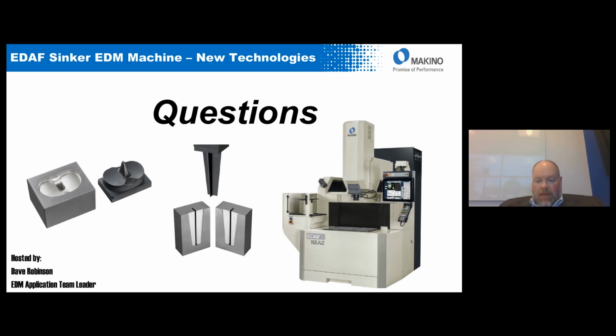Another question. We have a 2019 EDAF 3 heat. Do you recommend using a manifold to move the fluid more in the work tank? On the older machines, yeah, it's not a bad idea to use a manifold system to move that oil around. One of the problems, though, is when you do use a manifold system, you really have to watch running the oil across the top of the workpiece, across the top surface, either from front to back, which is generally the preferred method, or side to side if you have to. Setting up a manifold where that flow pushes the debris down into corners and pockets where it can get trapped can actually be counterproductive to the system.